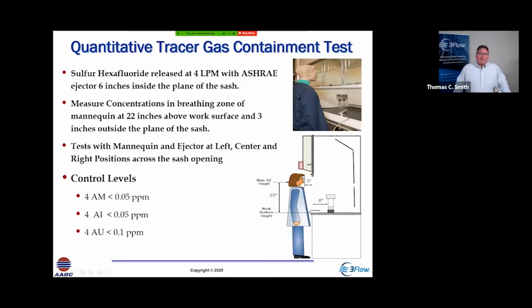So next comes the quantitative test. We've evaluated it qualitatively with smoke, but now we want to quantitatively test the hood. Is it containing under a challenge where we use a mannequin to simulate a person standing in front of the hood? We generate a tracer gas in the hood. The ejector is placed 6 inches behind the plane of the sash. The mannequin is 3 inches outside of the plane of the sash. We generate our gas at 4 liters per minute, and we leave the mannequin in place for 5 minutes, taking a breathing zone sample every second.